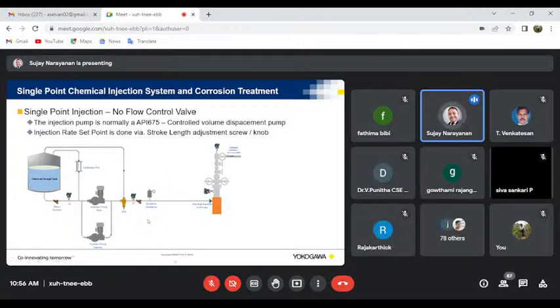Okay, that's the reason. So here you see there is no flow meter, no control valve, nothing over here. So the pump is doing two functions: it is maintaining the desired pressure, and it is also trying to control the flow rate. For example, if you say 20 liters per hour, it will try to discharge 20 liters depending upon the stroke length you set.